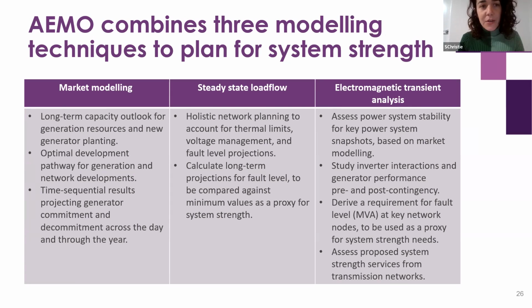That is based on what we get out of the market modelling, who we think will be online. And then we use load flow to look at what that might mean for fault level available on the system. We try to calculate those long-term projections for fault level, and then we compare them against the minimum values that we've decided would be the minimum amount required for system strength services to be met.